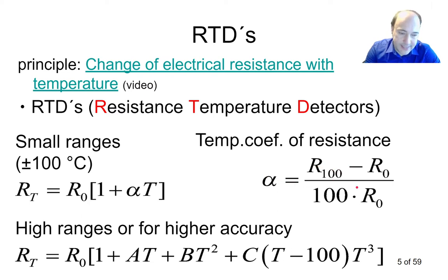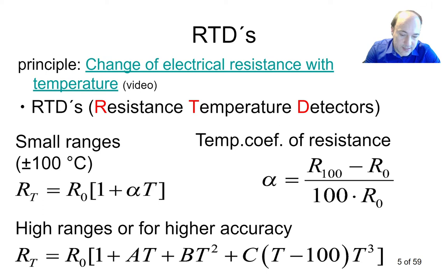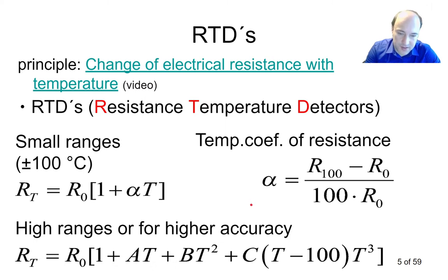For higher accuracy or a larger temperature range, we need a more complex equation with additional coefficients: A, B, and C. This equation is no longer linear — it includes T-squared and higher-order terms. If you want to describe the dependence of electrical resistance on temperature in a larger range, you need this type of equation. This formula is valid only for platinum; for nickel, for example, you would need even more coefficients.